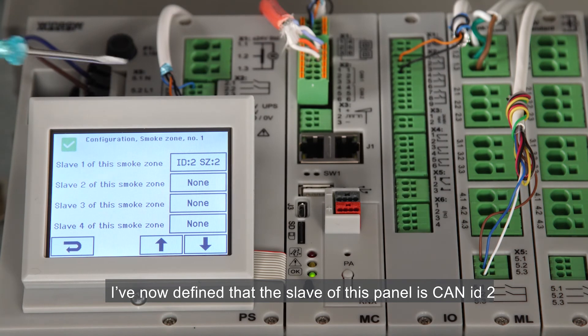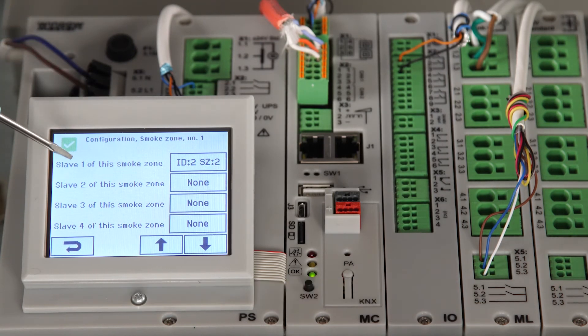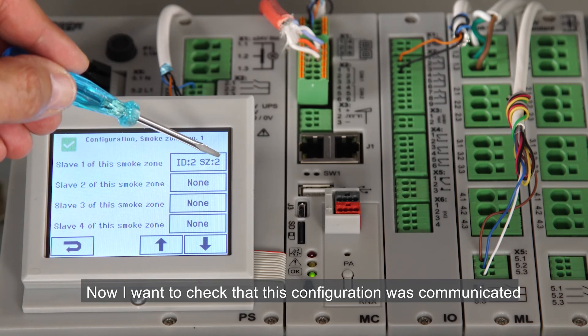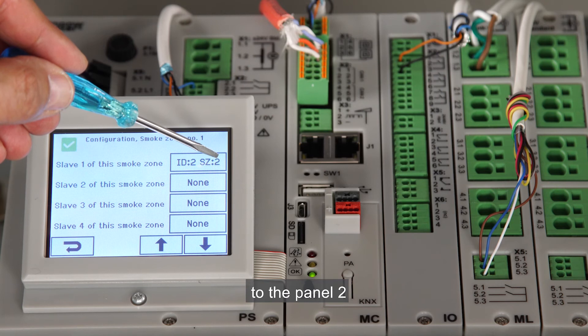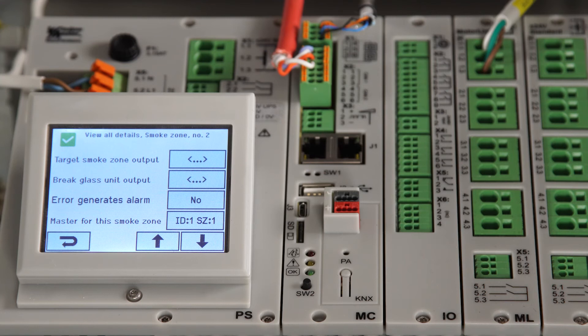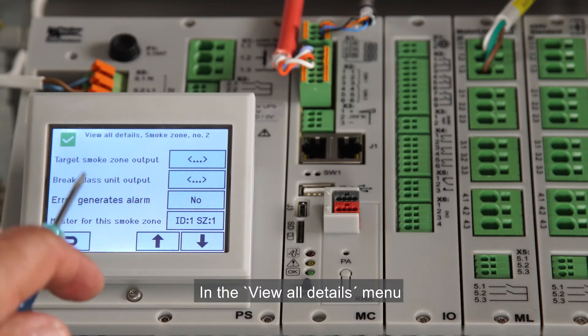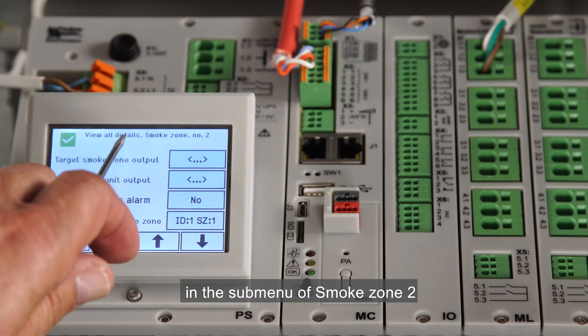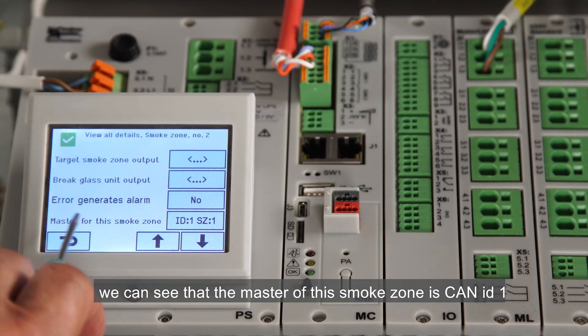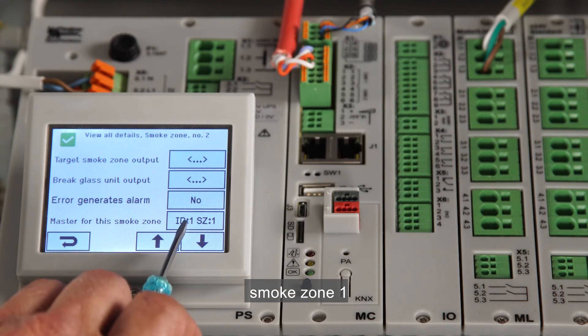I've now defined that the slave of this panel is CAN ID 2, smoke zone 2. Now I want to check that this configuration was communicated to panel 2. In the view all details menu in the submenu of smoke zone 2, we can see that the master of this smoke zone is CAN ID 1, smoke zone 1.